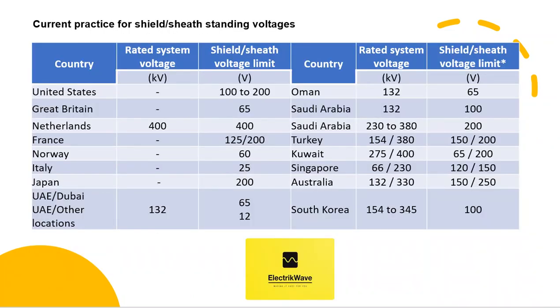Country-wise current practice for shield or sheath standing voltages: the maximum sheath voltage value ranges from 25 volts to 250 volts under normal operating conditions. Values of sheath voltages during emergency operating conditions vary by country and are in the range of 275 volts to 600 volts.